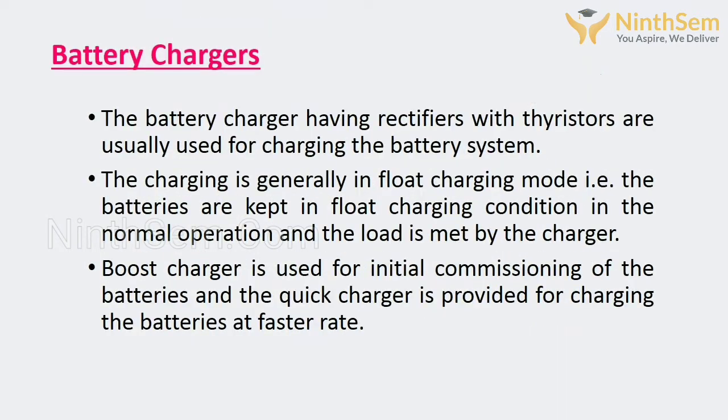Battery chargers having rectifiers with thyristors are usually used for charging the battery system. The charging is generally in float charging mode, that is, the batteries are kept in float charging condition in normal operation and the load is met by the charger. Boost charger is used for initial commissioning of the batteries and the quick charger is provided for charging the batteries at a faster rate.